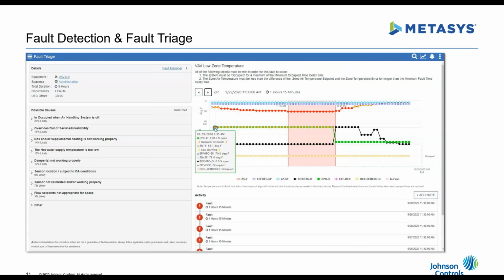You'll notice the chart color is filled in with the Metasys color for override. As he overrode it, the temperature, shown above in yellow, first went into low warning, then into alarm, until it reached its fault area. The shaded pink area is the actual duration of that fault.